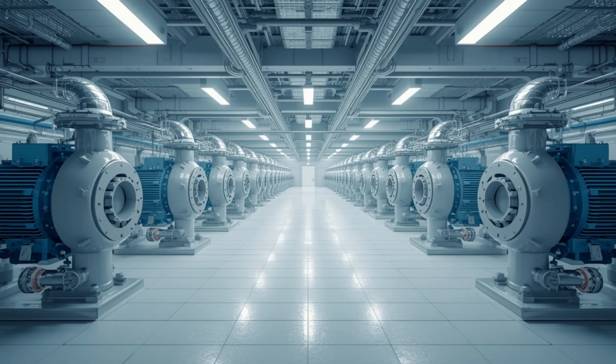During backwashing, flow is reversed. Water is pumped upward through the sand bed at high velocity, fluidizing the sand and flushing accumulated debris out through a waste line. Backwashing lasts for 8 minutes and consumes approximately 250 gallons of water, but it's necessary to maintain filtration efficiency. Third stage, biological treatment.